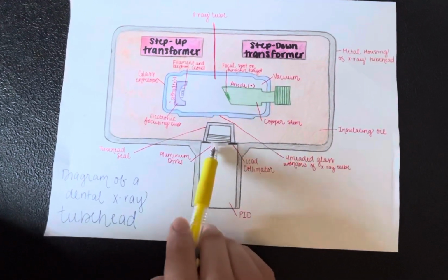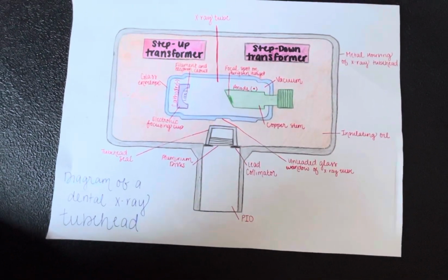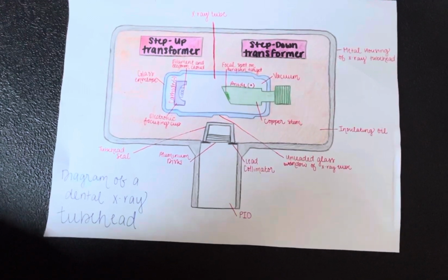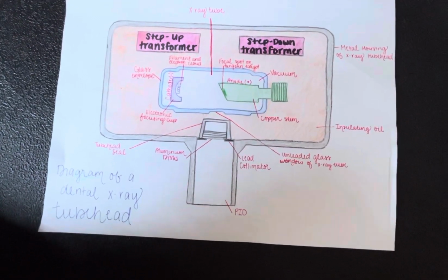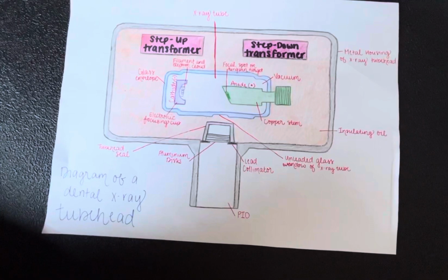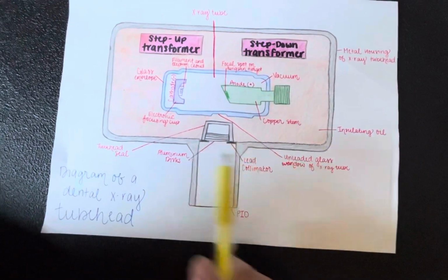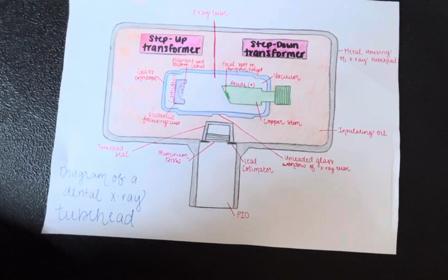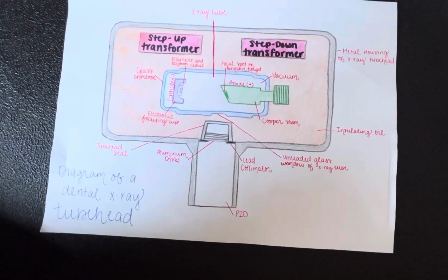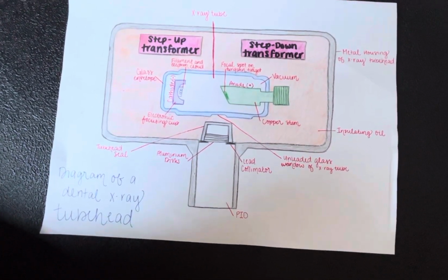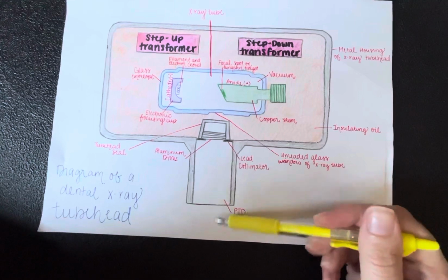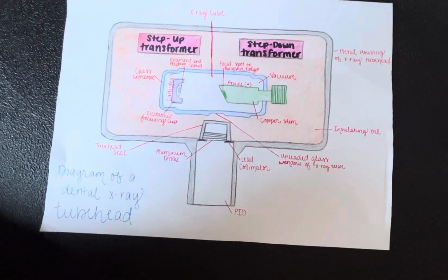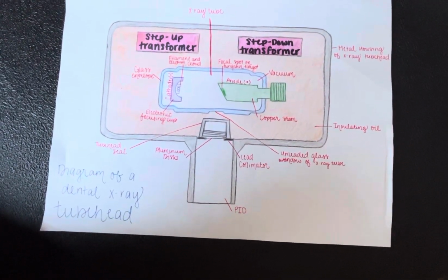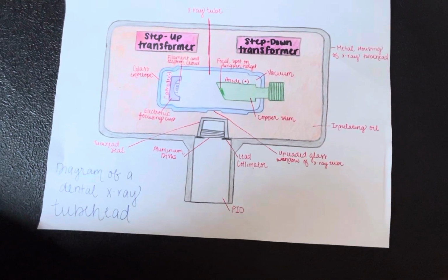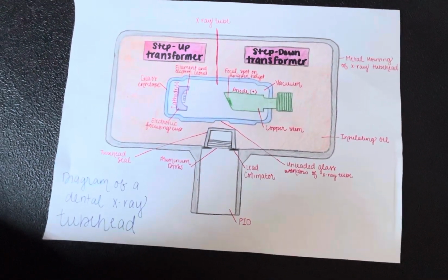Aluminum discs. These are sheets of 0.5 millimeter thick aluminum placed in the path of the X-ray beam, and they filter out the longer, less powerful X-rays. The lead collimator is a lead plate that has a little opening in it, and it restricts the size and shape of the X-ray beam. The position indicating device, or PID, is an open lead-lined cylinder that extends from the opening of the tube head. It aims and shapes the X-ray beam.